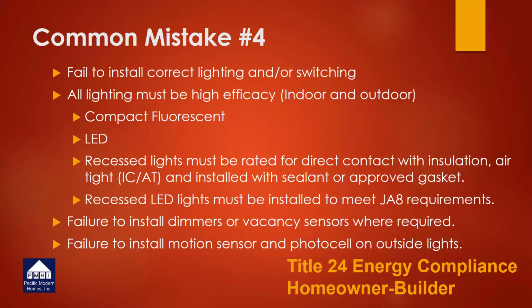Failure to install dimmers or vacancy sensors where required is a real common issue. They are listed for you on the drawings that you receive from PMHI. However, if you do fail to put in the right one and the building inspector catches it, it's a fairly simple change to pull out the old switch and put in the appropriate one. A little bit of delay, a little bit of cost, but it's not a catastrophic failure.